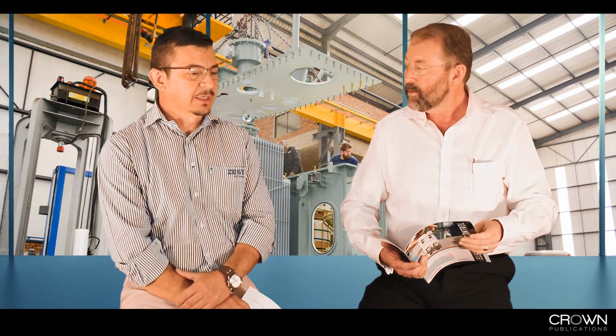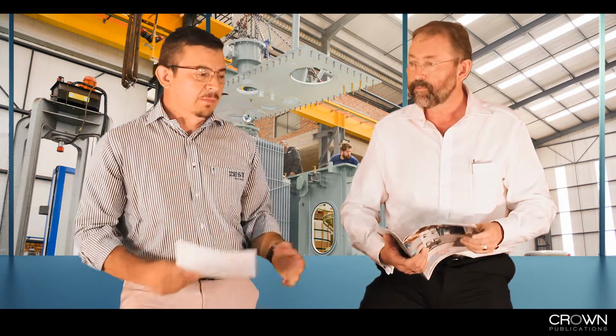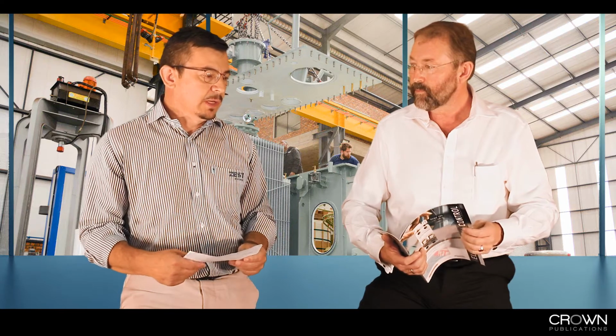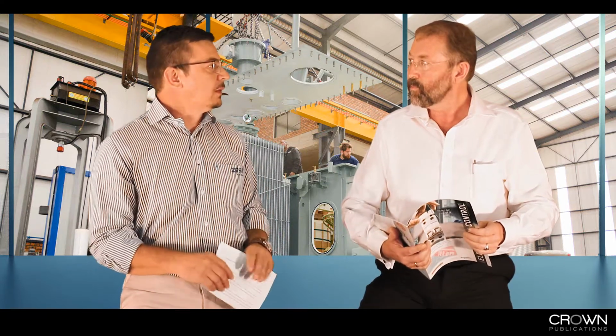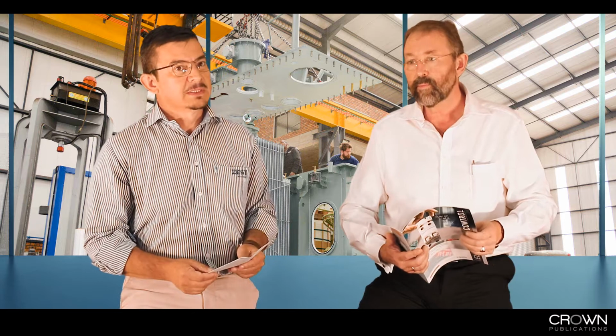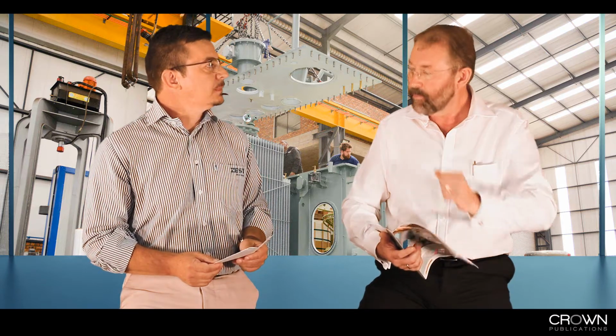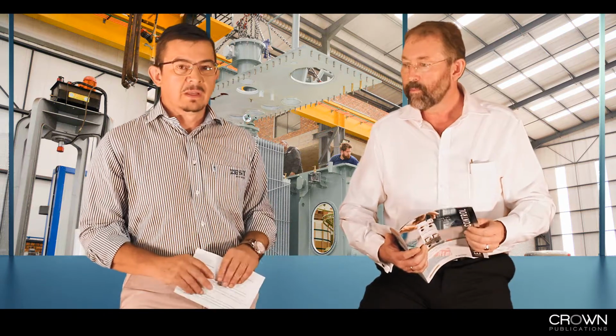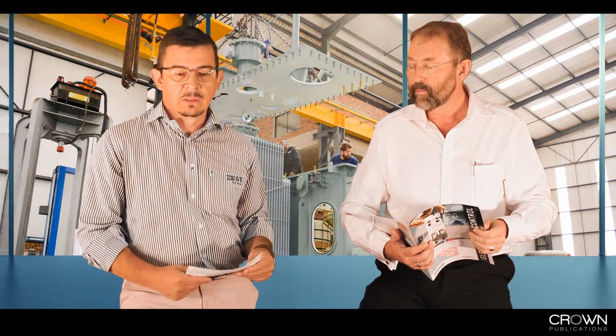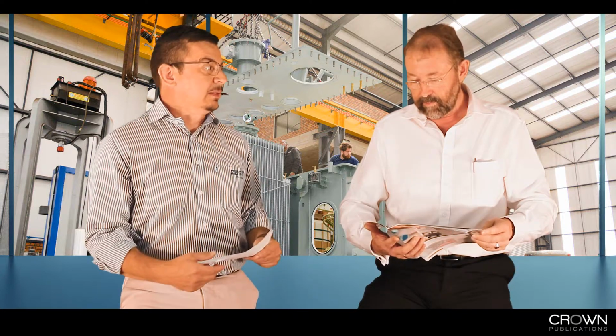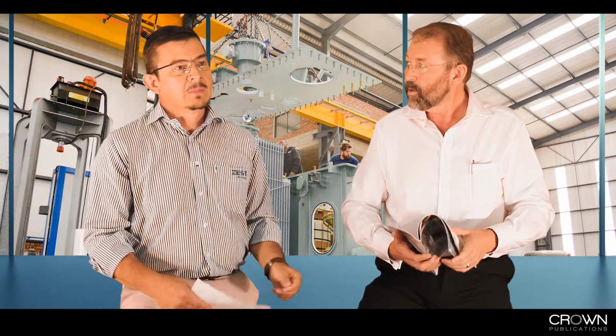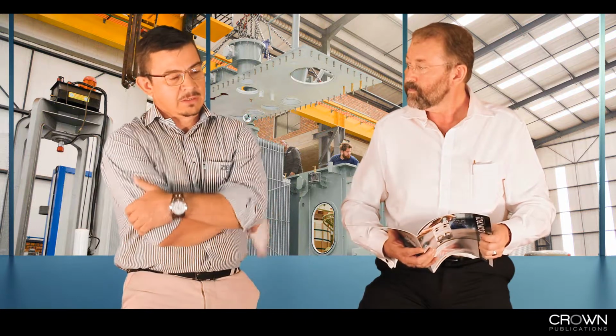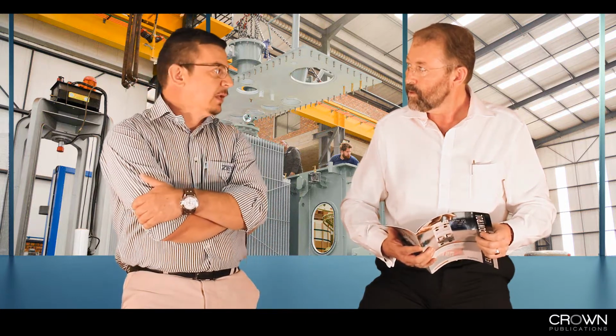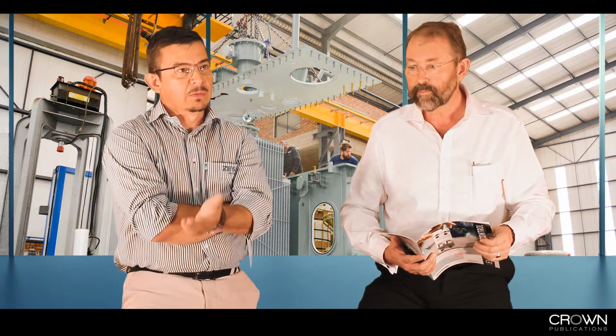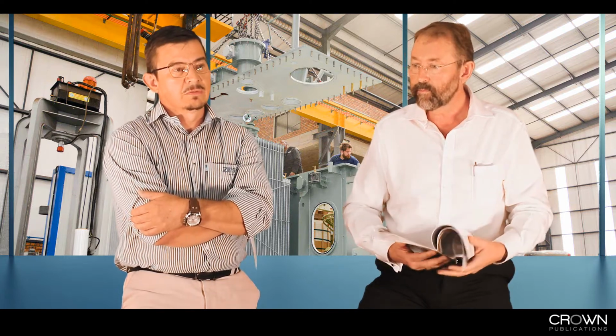Yes, 100%. As with every other equipment, what limits the life of a transformer is the temperature—that's the biggest killer. The temperature greatly affects how the operation will work and the life expectancy of the transformer as well, because the insulation is the weak part of the transformer, and the insulation depends on the temperature at which it's going to operate.